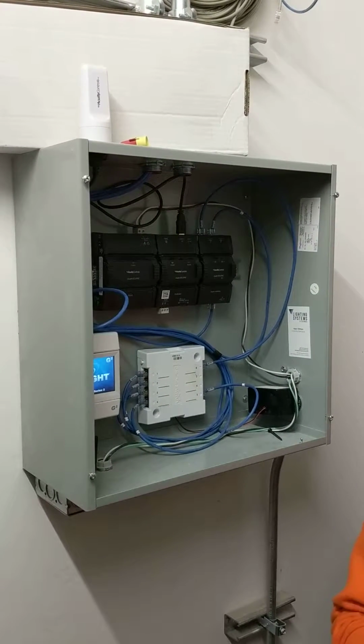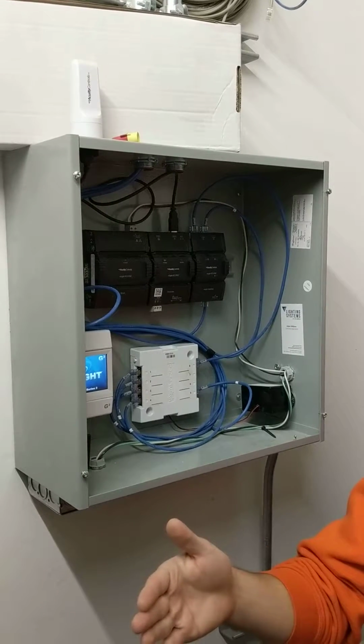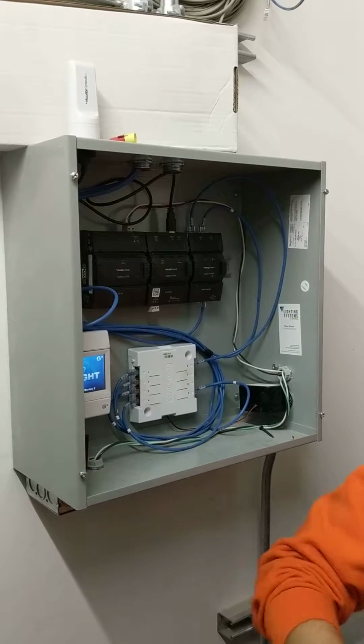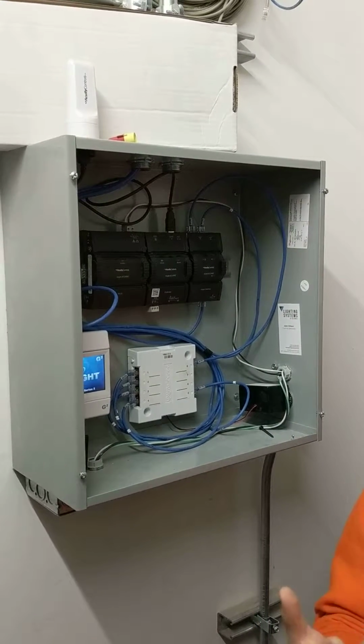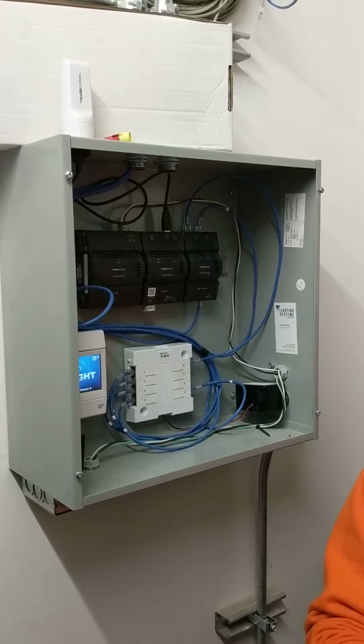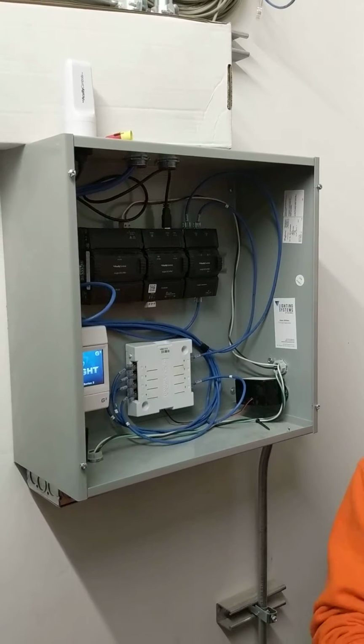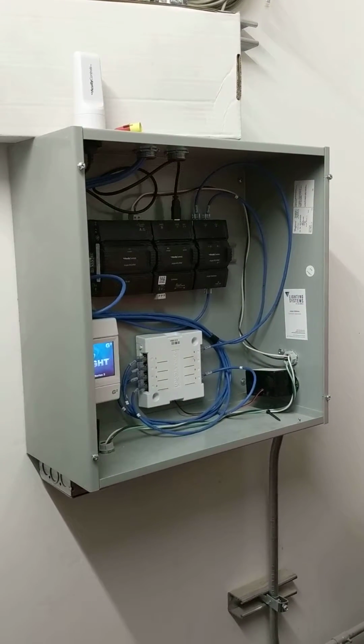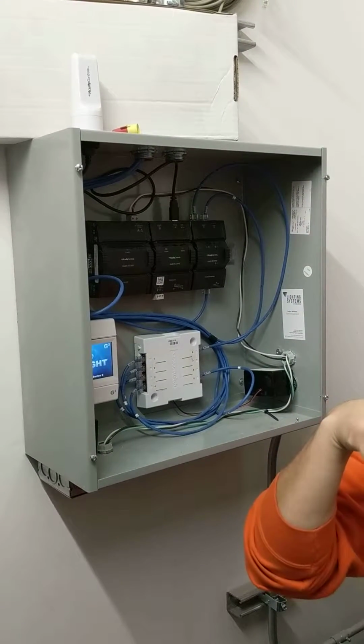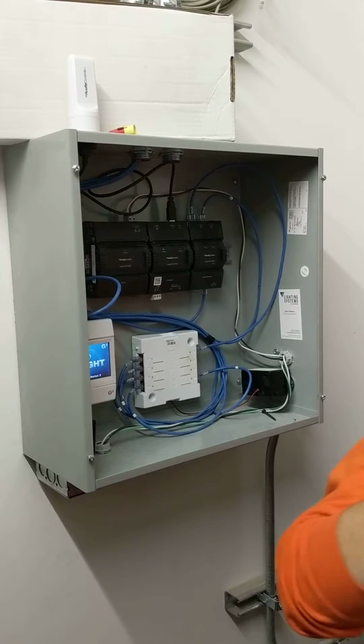The override on command will end, and then it'll be taken over by the occupancy sensors. So as long as somebody's still in the space, the sensor is going to still read them. Can you turn it off during that time? I can have it turn off itself and manually override a power off. The only downside is if somebody's sitting in the middle of the room, the lights will turn off on them. Then they'd have to get up and walk over and turn on the lights. So just as a heads up, that's kind of how it works.